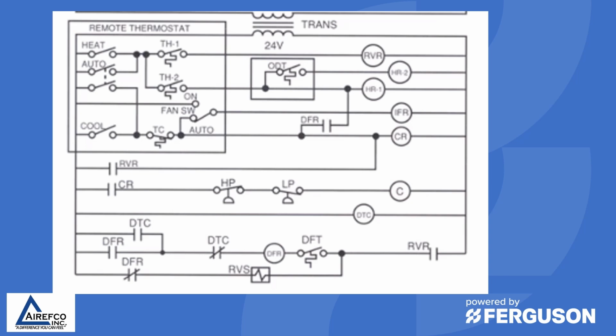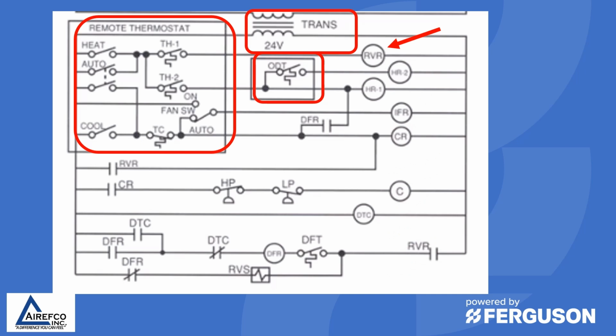Now let's look at our 24 volt system. We have a 24 volt transformer that powers our control circuit. We have a thermostat that is wired into this system with thermostat switches that open and close on temperature rise and temperature drop. We have an outdoor thermostat which is connected to the heat strips, which will prevent the heat strips from coming on until the temperature is at a certain degree. We have the reversing valve relay. We have the defrost relay. You have your heater relays that energize the heat strips, as we saw in the upper diagram. There's your indoor fan relay, your control relay, your reversing valve contacts that are operated off the RVR coil.